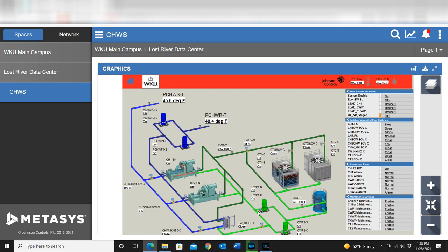This is a very robust system. This is just a basic overview of how a plate frame chilled water system works, in conjunction to provide a cool water supply year round. I mean, this system runs in the middle of winter. The chillers, of course, will be down, but we will be running on plate frame, using that cooler outside air to cool and provide chilled water for the system.